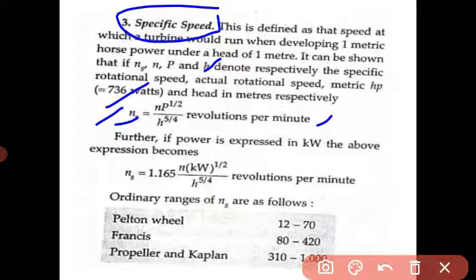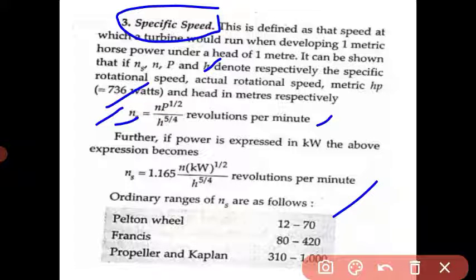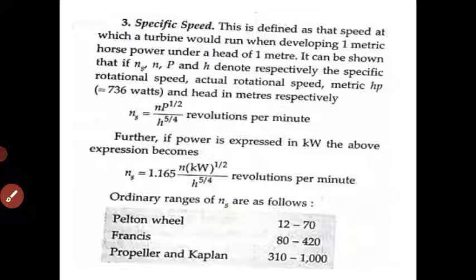The ordinary range of specific speeds Ns are: Pelton wheel 12 to 70, Francis turbine 80 to 420, and propeller and Kaplan type 310 to 1000 rpm.